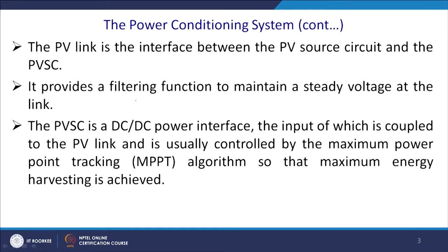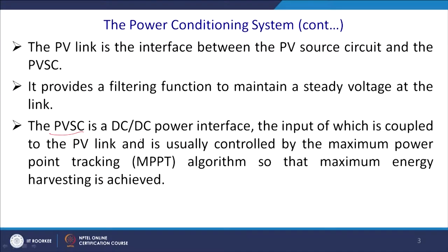The PV link provides a filtering function to maintain steady voltage at the link. In a boost converter, when shorting occurs, we require a filter so that the current value does not fluctuate to a very high extent. The PVSC is a DC-to-DC power interface whose input is coupled to the PV link and is usually controlled by the maximum power point tracking algorithm so that maximum energy harvesting is achieved.